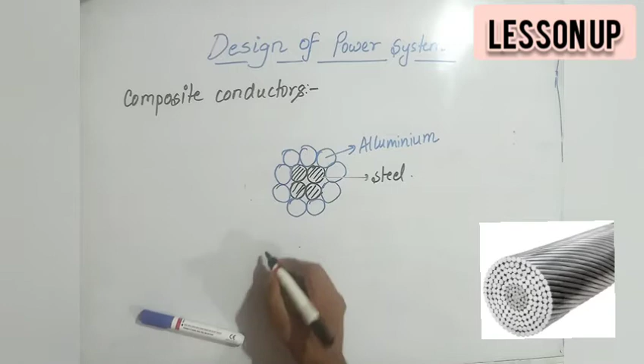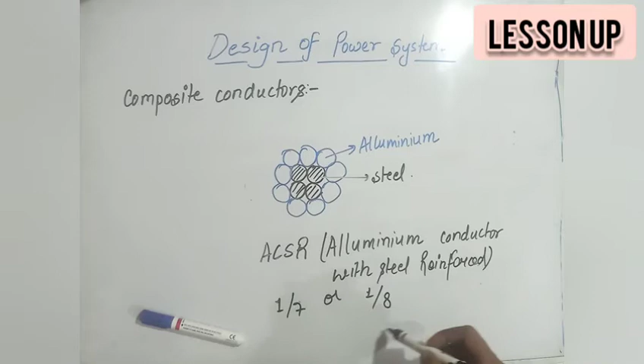Thereby, its mechanical strength should be improved. For that, the central portion is reinforced with steel strand over the aluminum strand. As you can see in this picture, in the center portion of the conductor we are using steel over the aluminum conductors. This provides mechanical strength to the conductor, and this type of composition is called ACSR, which means aluminum conductor steel reinforced, and the proportion is 1:7 or 1:8. That is, 1 strand of steel wire with 7 strands of aluminum wire, or 1 strand of steel wire with 8 strands of aluminum wire.